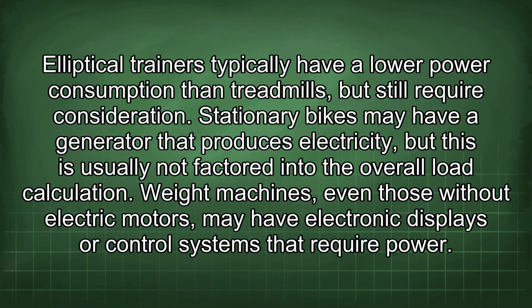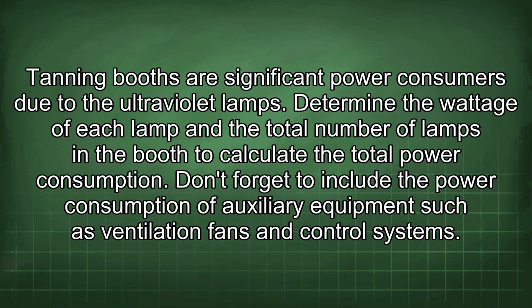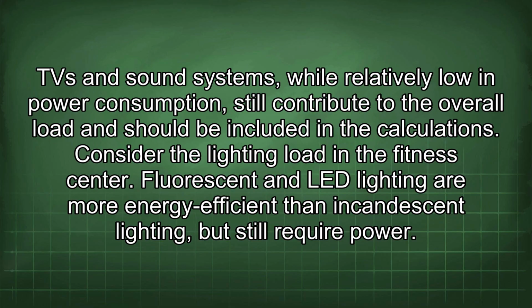Weight machines, even those without electric motors, may have electronic displays or control systems that require power. Tanning booths are significant power consumers due to the ultraviolet lamps. Determine the wattage of each lamp and the total number of lamps in the booth to calculate the total power consumption. Don't forget to include the power consumption of auxiliary equipment such as ventilation fans and control systems. TV and sound systems, while relatively low in power consumption, still contribute to the overall load and should be included in the calculations. Consider the lighting load in the fitness center. Fluorescent and LED lighting are more energy efficient than incandescent lighting, but still require power.